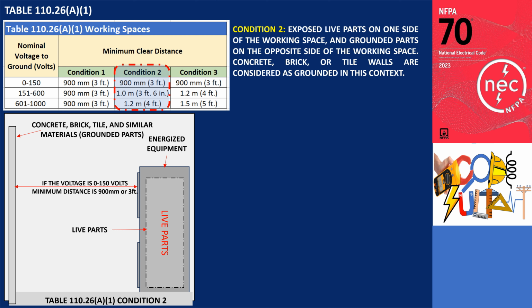In cases where the voltage falls between 151 and 600 volts, the minimum clearance distance increases to 1 meter or 3 feet and 6 inches. For voltages ranging from 601 to 1000 volts, the minimum clear distance is 1.2 meters or 4 feet.